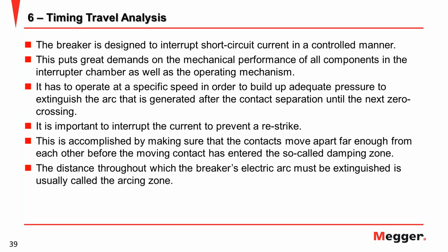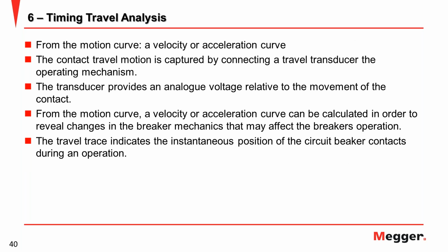Okay, and the timing travel analysis. This is also an additional test, similar to the breaker timing test, but mostly to detect mechanical problems on the breaker. In this testing, we need to connect specific accessories. We call it a transducer. You need to connect it as close as possible to the mechanical part of the breaker. There are 2 types, linear or rotary, depending on how the breaker moves.